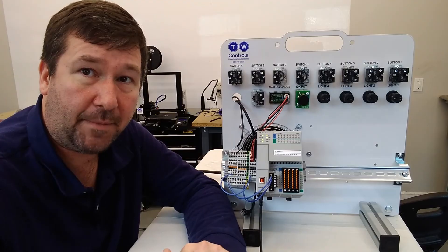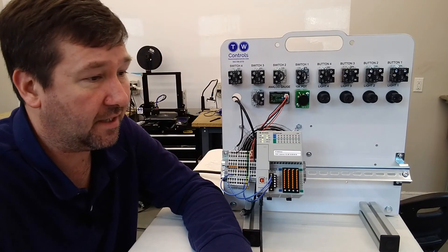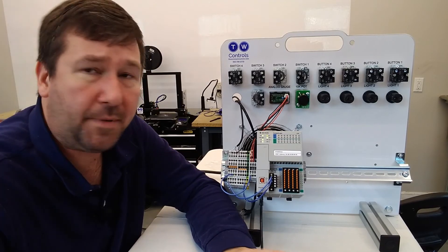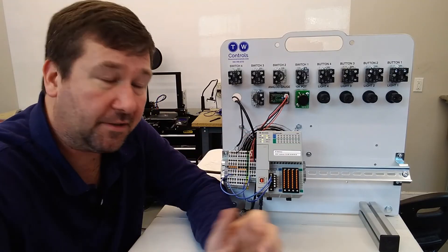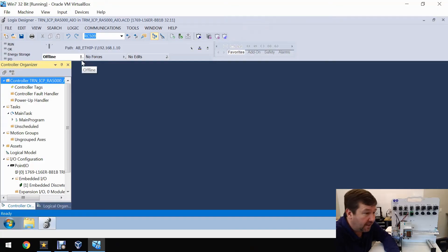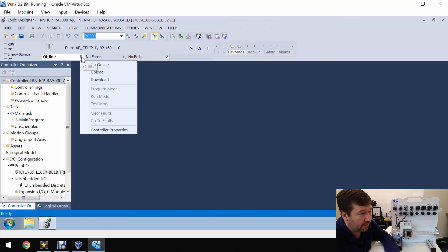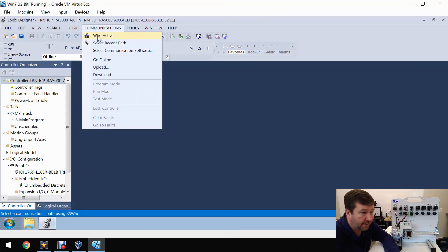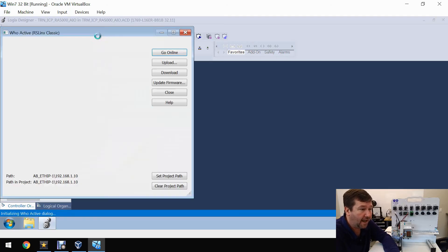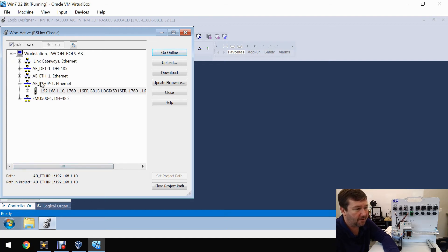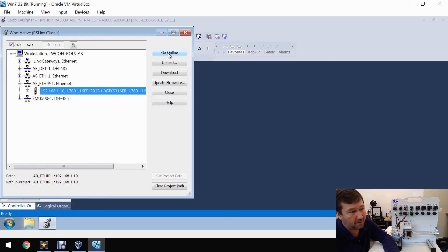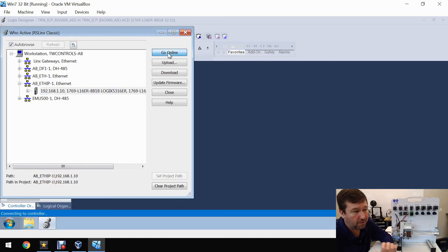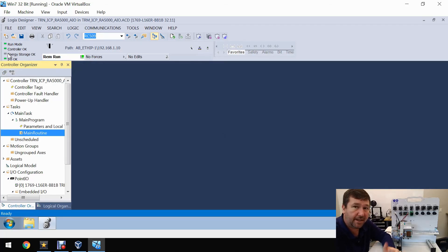Let's go ahead and use the Ethernet IP driver and go online for PLC. We're going to open up our Getting Started program that comes with all our PLC trainers. There's several ways to go online. You could click right here and go online, or you can go to communications and go online. But I like to use this WhoActive because it gives you all the options and lets you make sure you're able to navigate to the path you want. We click on our Ethernet IP driver, there's our PLC, and we're going to click go online. And we're online. We're in remote mode, controller is okay, IOs is okay.